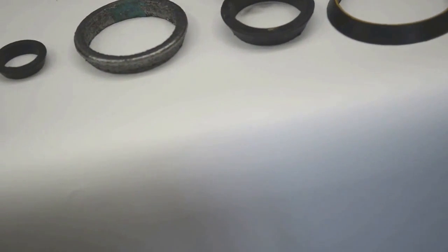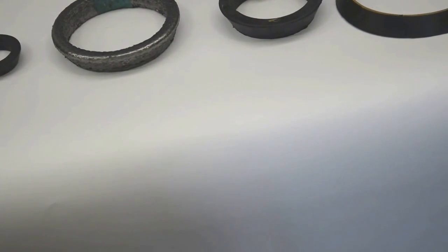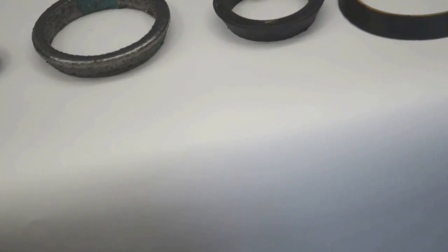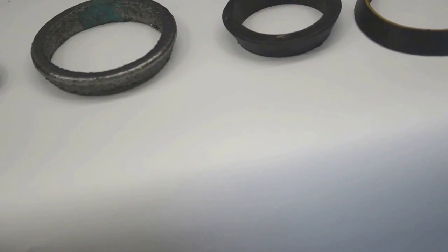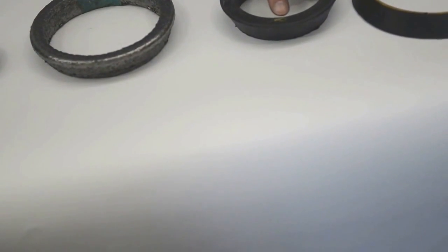Next to that, this is a grade 42 gasket. That's a Buna N gasket for oil service, generally. It's color-coded with a yellow dot.